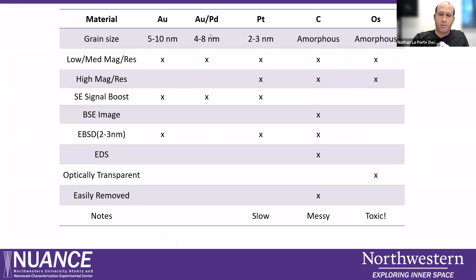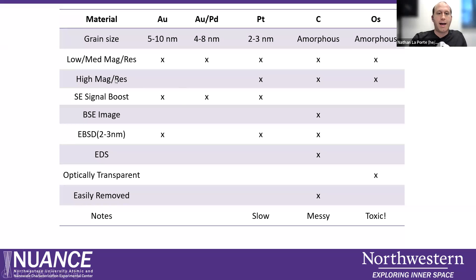Let me talk about the different materials and their pros and cons. In terms of grain size, gold gives the biggest grains, then gold-palladium, platinum, and carbon and osmium are amorphous, giving you the smallest grain size. Gold, palladium, and platinum are all suitable for low or medium magnification and resolution. If you have really high magnification or resolution needs, you're going to need to use either platinum, carbon, or osmium. Our rule of thumb is that if your feature size is smaller than 100 nanometers, you want to use the osmium coater. On the other hand, you can get a boost of secondary electron signals by using some of the metals — so if that's important to you, you'll want to use gold, gold-palladium, or platinum.